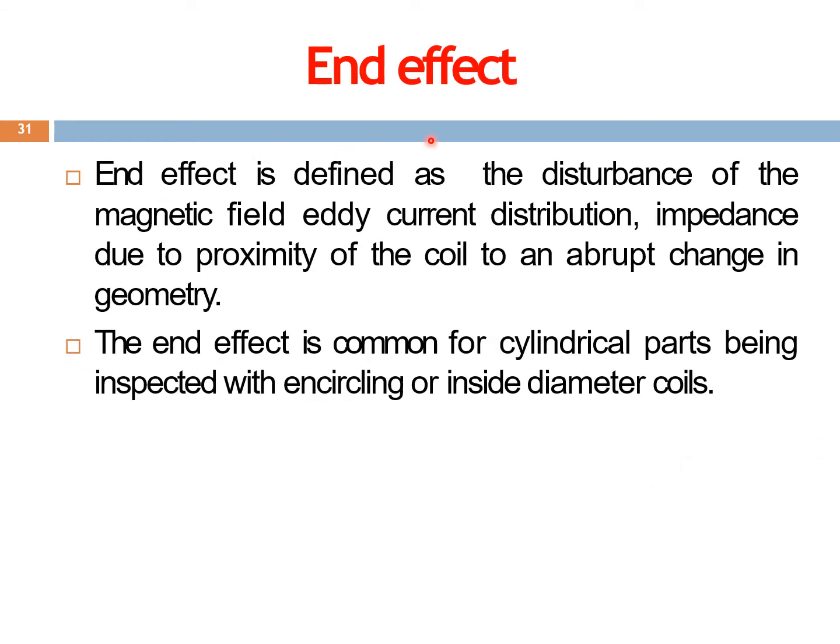Okay, and the end effect is also there. End effect, as you know, is similar to the edge effect. The end effect is common for cylindrical parts, right? At the edges, there will be area changes. So these area changes will be identified as false defects in the measurements. So again, we will limit it to the surface, and the inspection is carried out closer towards the surface and away from the edges as much as possible.